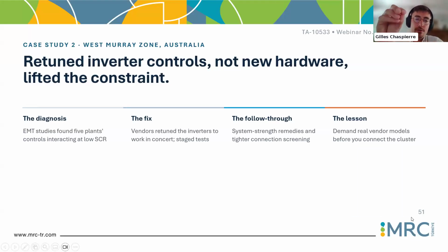And now what I would like you to understand is that I expect in the future that a lot of TSOs will face similar issues, simply because the grid is evolving faster than expected. When an asset connected 10 years ago, it had a proper study to make sure it would not, of course, destabilize the grid, but over a given operating range of the system. And most of the time, we are now entering a period where the grid is going outside of this operating envelope for which the asset has been designed. And so the control is no longer adapted. It has not been tuned robustly enough to deal with a weak grid, basically.